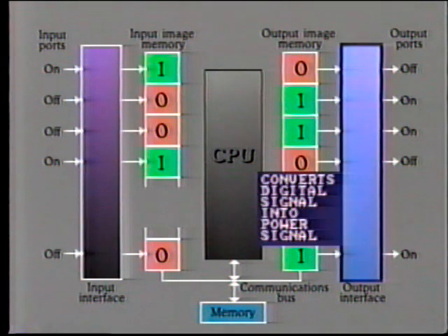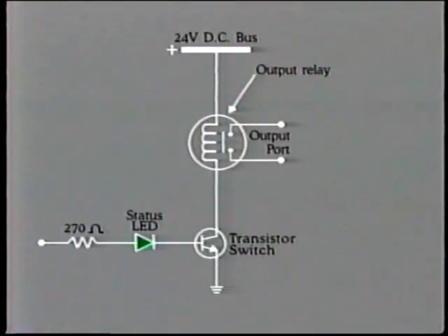Its main function, then, is to convert the CPU's digital output signal into a power signal at the associated output terminal. This diagram shows one method using an electromechanical relay. The relay coil is connected across the internal 24-volt DC supply, and it is switched by a small transistor. This, in turn, is activated by an on signal from the CPU. Note that when this signal is on, it energizes a status LED. This provides the output indication that we spoke of earlier.